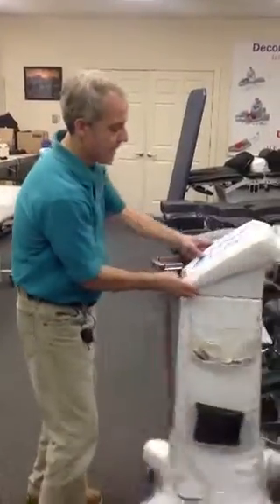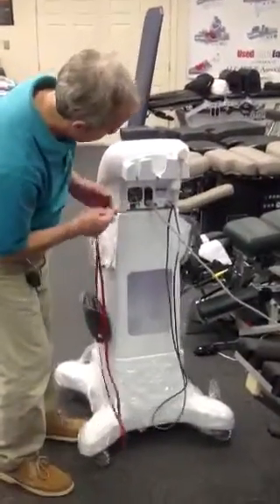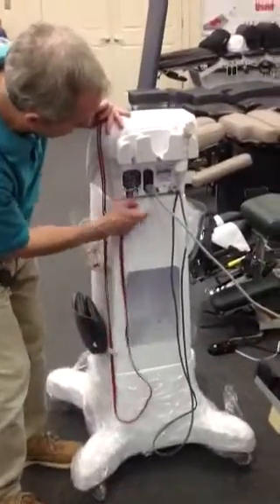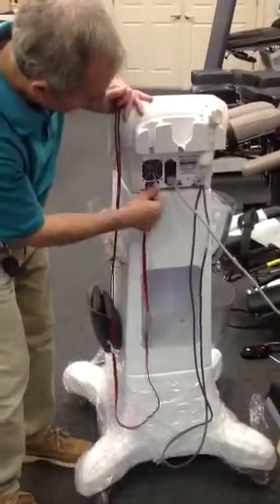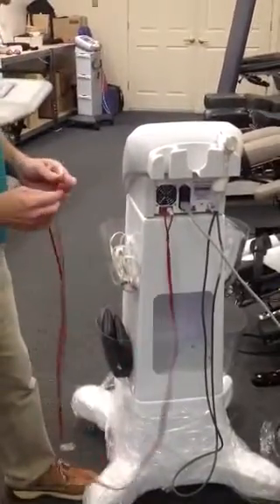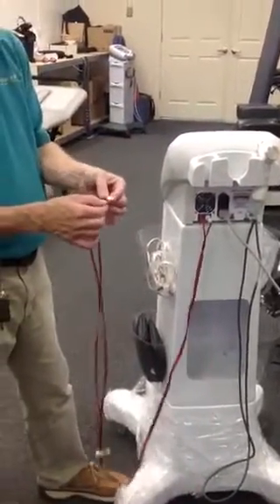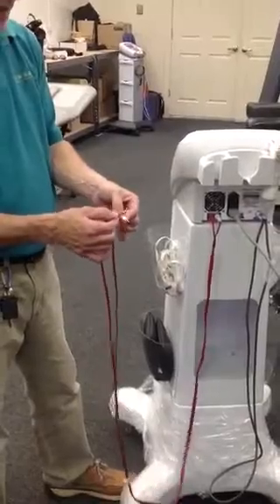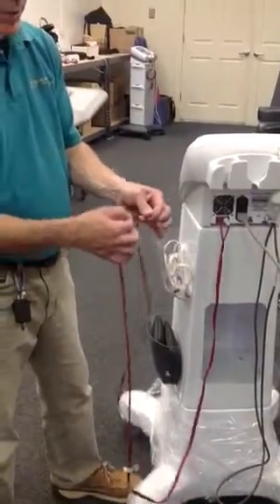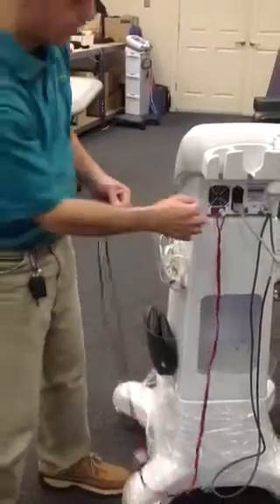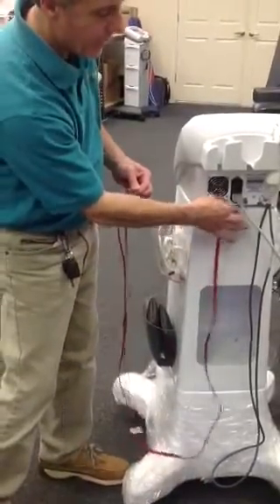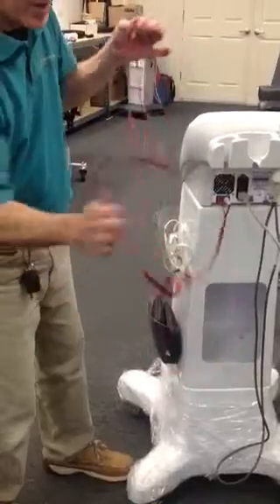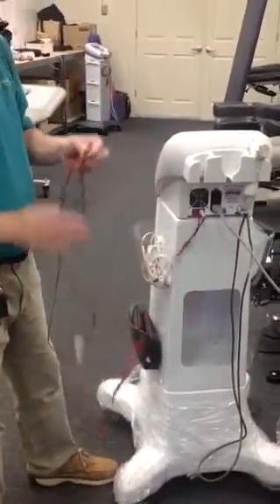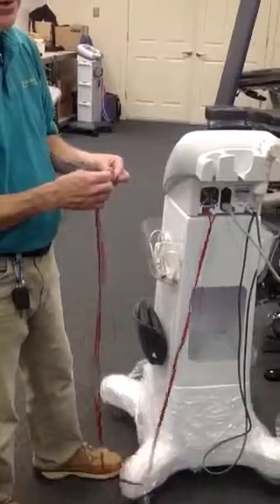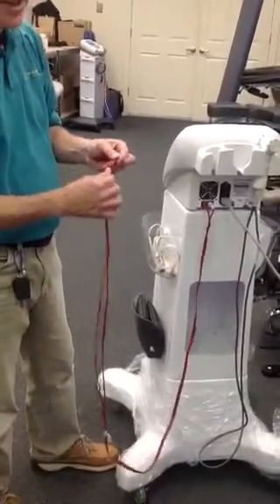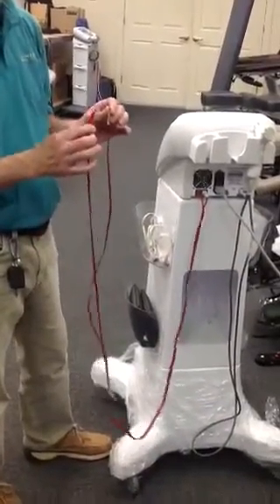But one of the neat things you can do on this particular machine is in the back you have an electrode test. And you plug it in, and there's a minor bit of electricity coming out of here, and you hold your 2 together. When you hold them together, you wiggle here, wiggle there, wiggle here, wiggle there, take it in the center, and shake it. The sound you're looking for is that sort of sound. If you get that sort of sound when you're wiggling, you know you have a break in the lead cord.